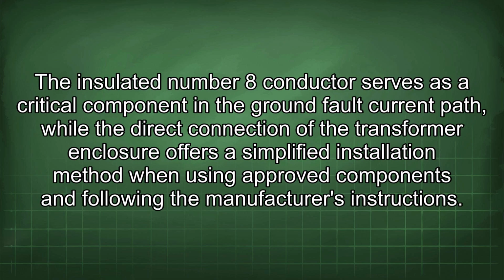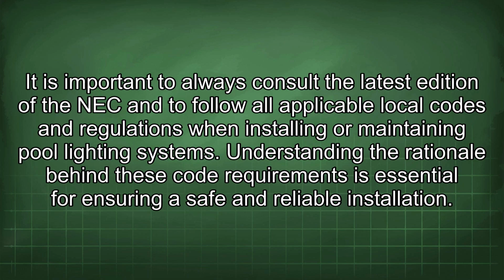The insulated number 8 conductor serves as a critical component in the ground fault current path, while the direct connection of the transformer enclosure offers a simplified installation method when using approved components and following the manufacturer's instructions. It is important to always consult the latest edition of the NEC and to follow all applicable local codes and regulations when installing or maintaining pool lighting systems. Understanding the rationale behind these code requirements is essential for ensuring a safe and reliable installation.